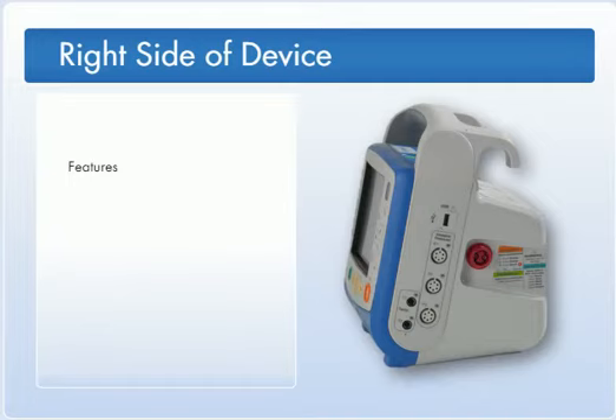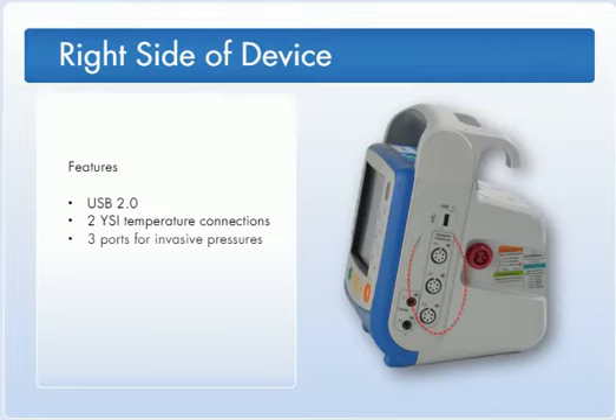The right side of the X-Series contains the ports for communications, critical care monitoring, and electrical therapies, including USB 2.0. Two YSI connections are located here in the front and can be used with esophageal, rectal, or surface temperature monitor probes. 3 optional channels with 6-pin cable connectors, known as AAMI connections, accept the most commonly used transducers for measurement of invasive blood pressures. There is also a multifunction cable port.